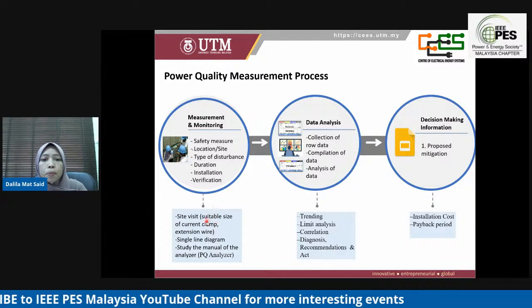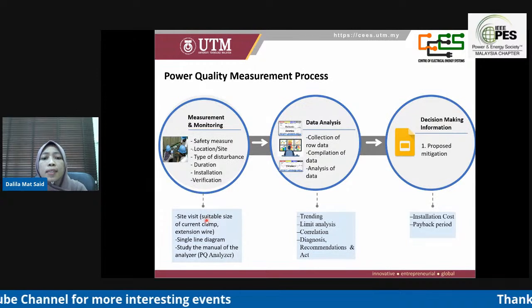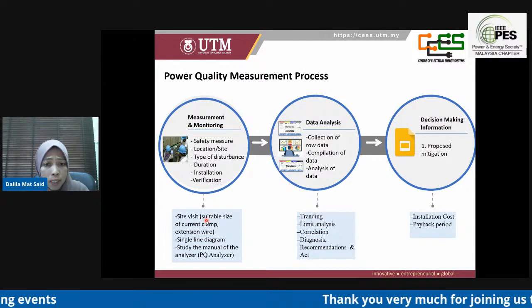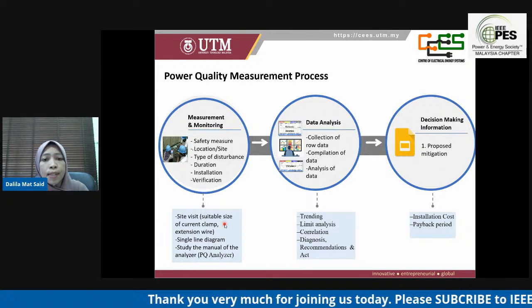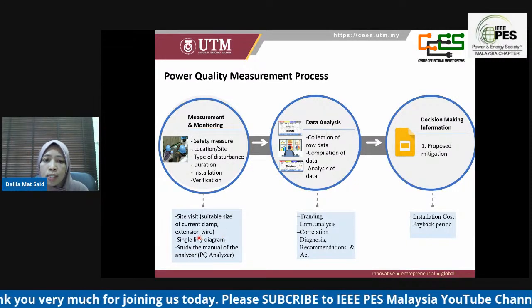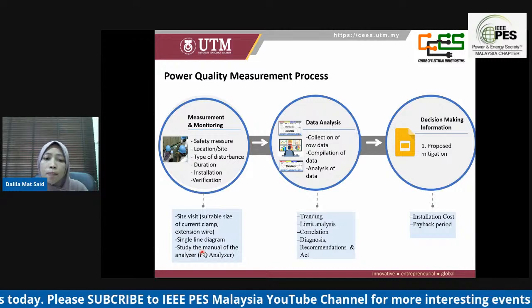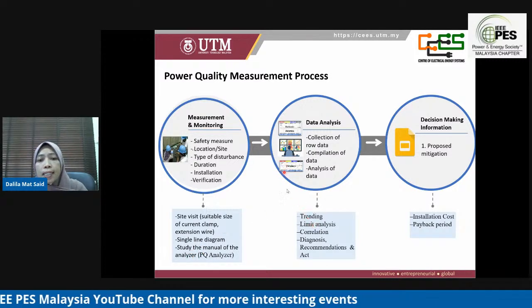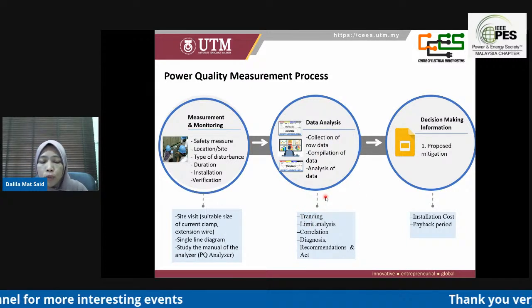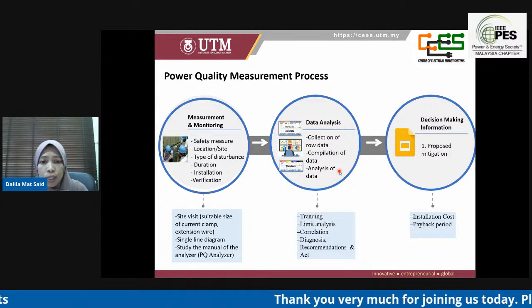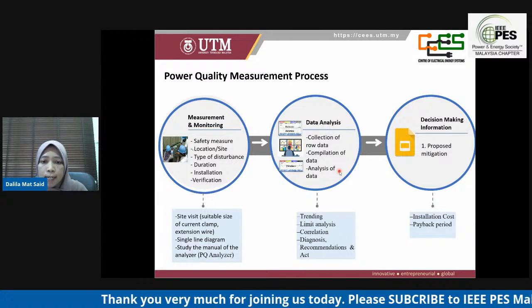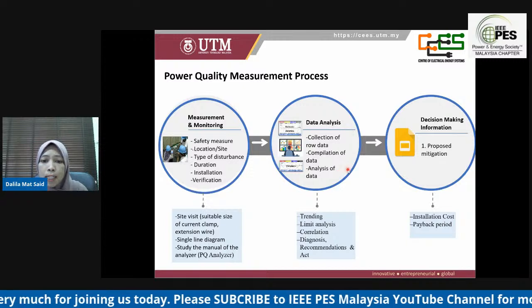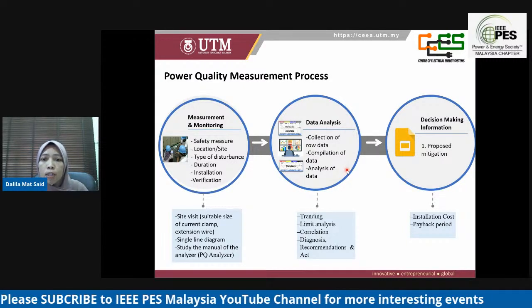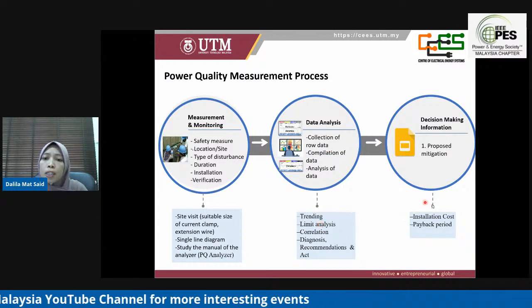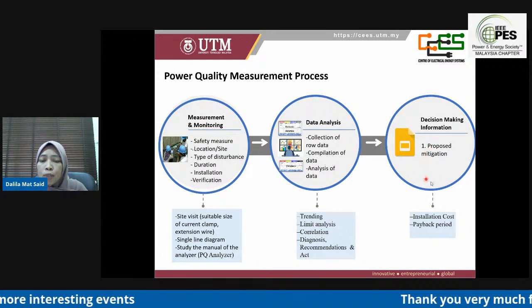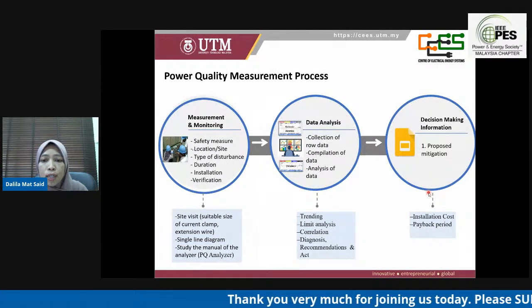Usually during the site visit, we can see and check what is the suitable size of current clamp, or whether we need to bring an extension wire during the installation. And during the site visit also, we will share the single line diagram, and of course, the person who wants to handle the monitoring device should study the manual and have expertise in how to use the PQ analyzer. For the data analysis, after we have transferred the data to the computer, usually most of the measurement devices come with software that we can use to take the data. Either we want to plot the trending, compare with the limit, or correlate the event with other events, and with enough data, we can propose a suitable mitigation. And for the mitigation, usually we can consider the installation cost for the mitigation and the payback period.